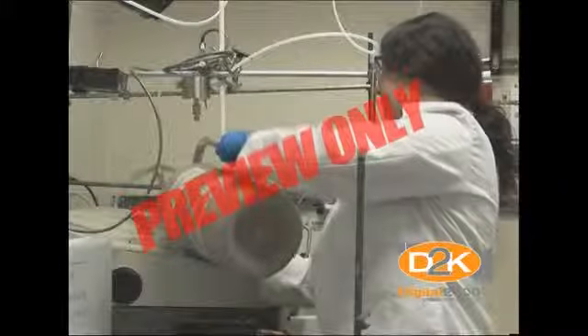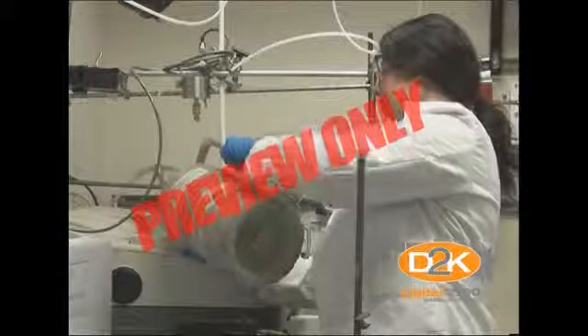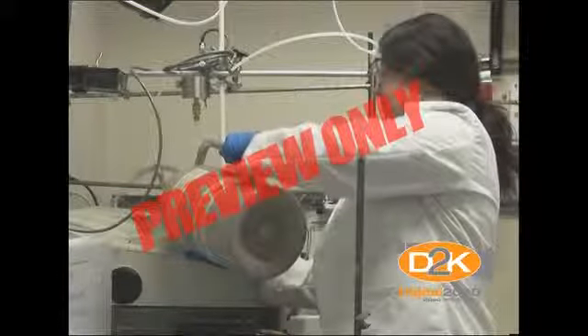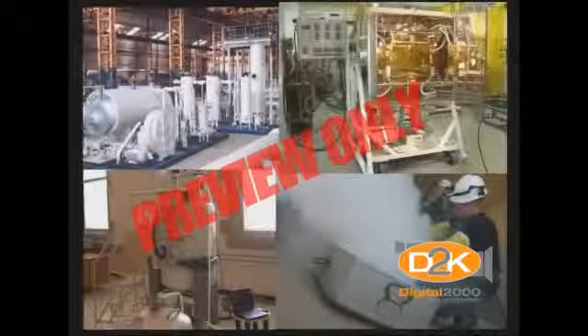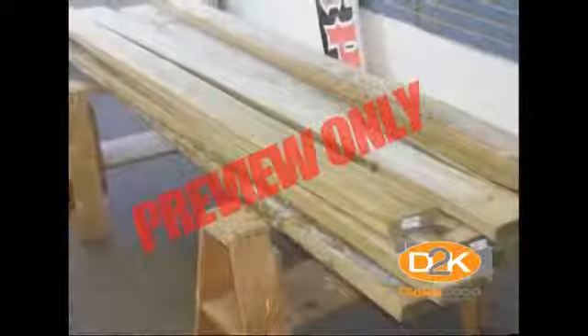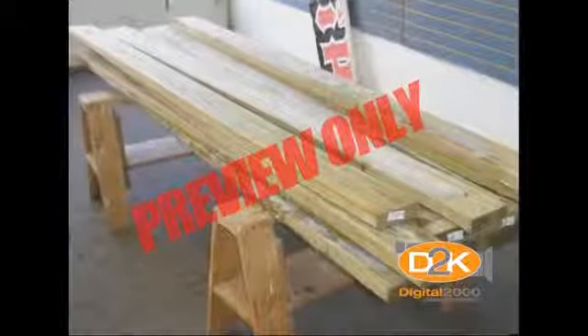Materials must be carefully selected for use in cryogenic service because of the drastic changes in the properties of materials when they are exposed to extreme low temperatures. Materials which are normally ductile at ambient temperatures may become extremely brittle when subjected to temperatures in the cryogenic range, while other materials may improve their properties of ductility. For example, you can use an overripe banana to hammer a nail into a pine board after it has been frozen with liquid nitrogen.